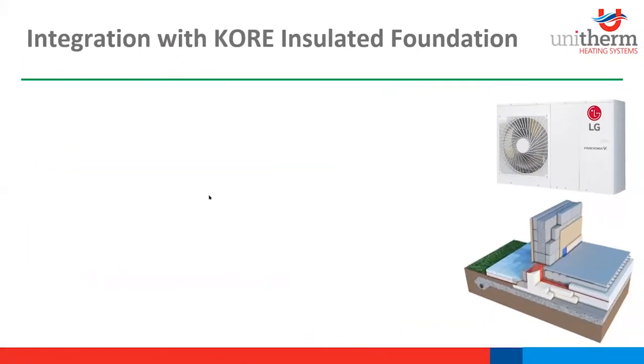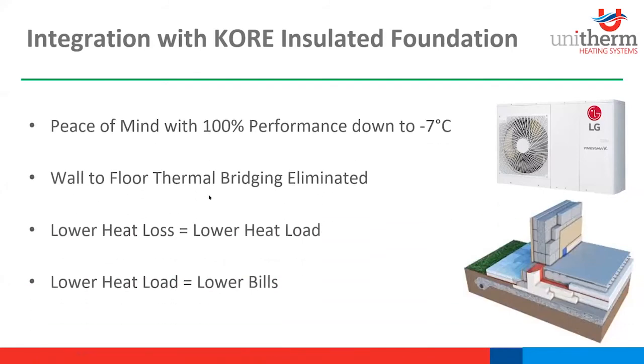Right, so integrating our underfloor heating system with our low temperature heat pumps and KORE's Insulated Foundation. As I said, complete peace of mind in those cold winter days with the LG Therma V, as you're guaranteed 100% performance down to -7. With KORE's Insulated Foundation System, exterior wall to floor thermal bridging is eliminated. And this gives your underfloor heating great relief at external walls and takes pressure off the system in those colder north-facing rooms. With floors and external walls being big contributors to heat loss, we've considerably lower heat load to consider, which lowers the required heating capacity and brings down the capital cost and running costs. So lower heat load, lower heat bills.